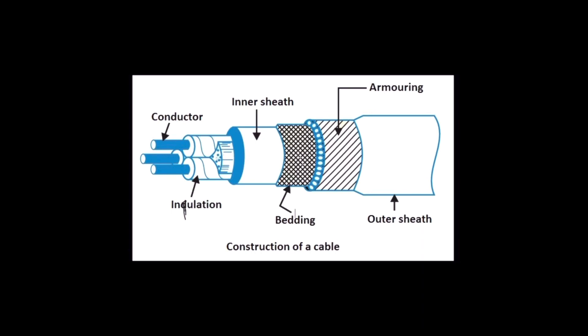This bedding is to prevent corrosion of inner sheath and around bedding there is a layer and there is armoring. Armoring is to protect cable from mechanical damages. It protects the cable from mechanical damages and the outer layer is called outer sheath.